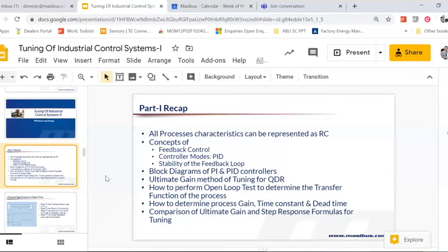Somebody wants to understand the Ziegler-Nichols method again. So the first method he put out, as I was explaining, is that you create an oscillation in the process. Now, how do you create an oscillation? One way is to operate it as an on-off controller, where you have maximum gain and no integral, no derivative.